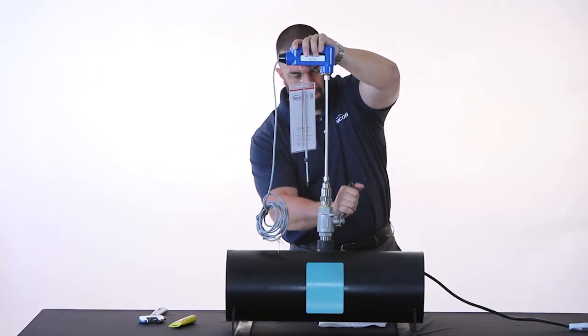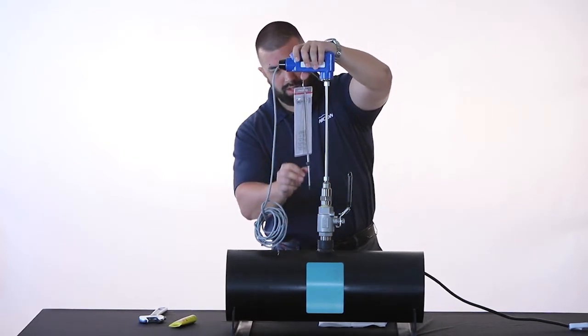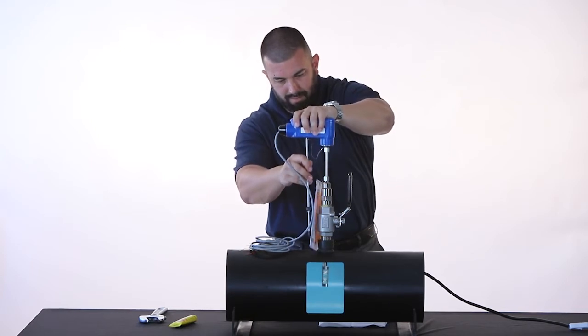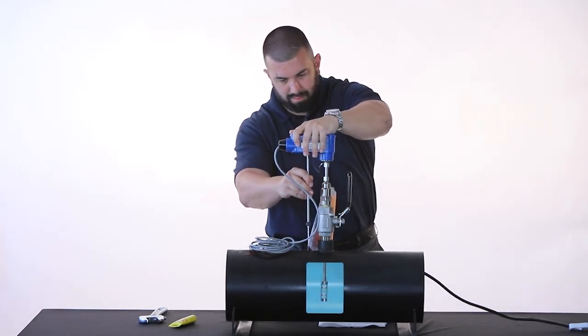Place the insertion depth gauge tip on top of the pipe, piercing through any insulation if needed. Gently push the flow meter down into the pipe until the other end of the insertion gauge touches the underside of the electronics housing.